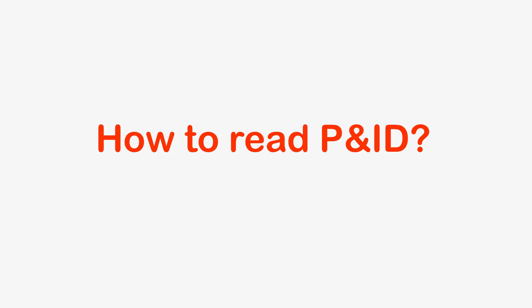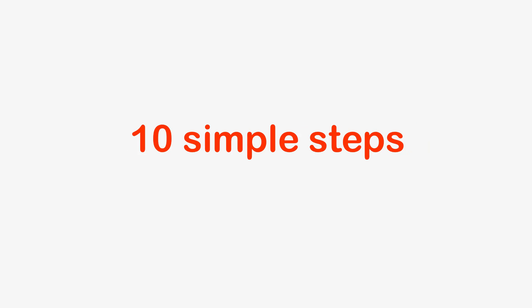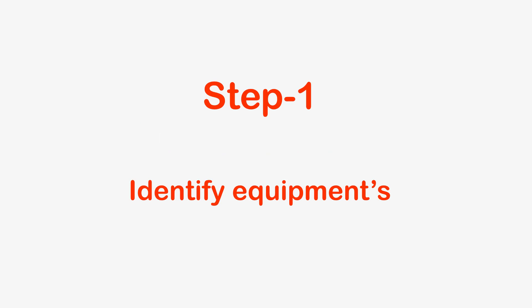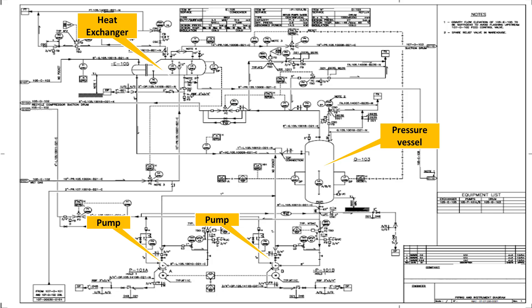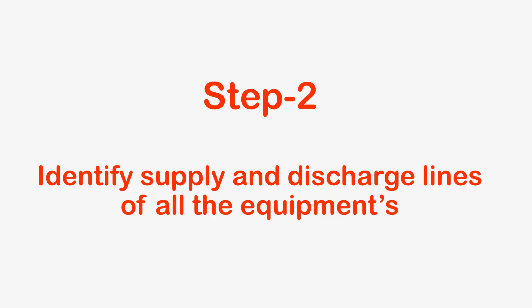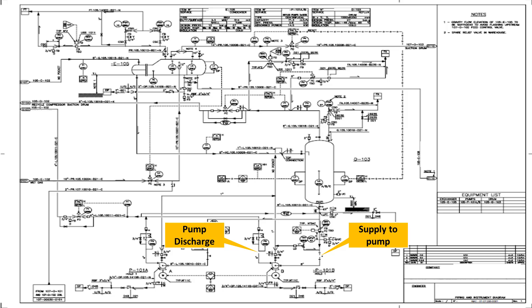Now we will see how to read the P&ID in 10 simple steps. Step 1: Identify Equipment. When you start reading a P&ID, the first thing to be done is to identify all the equipment. Step 2: Identify supply and discharge lines of all equipment. A P&ID may have more than one equipment, but it is better to identify the supply and discharge of one equipment first, then move on to another. Generally, equipment has a minimum of one supply and one discharge.